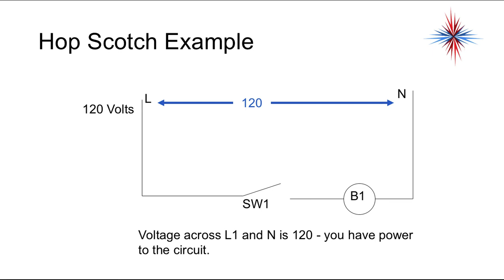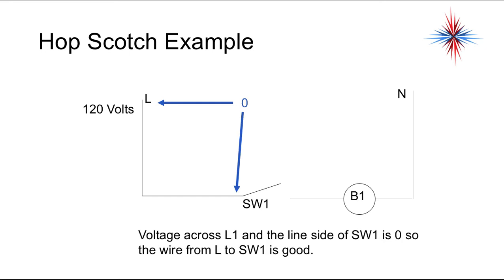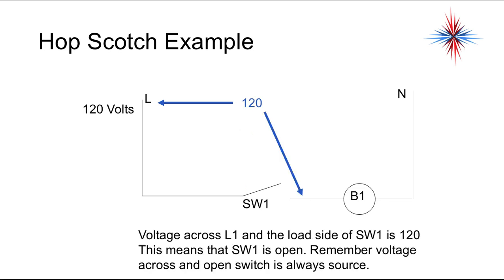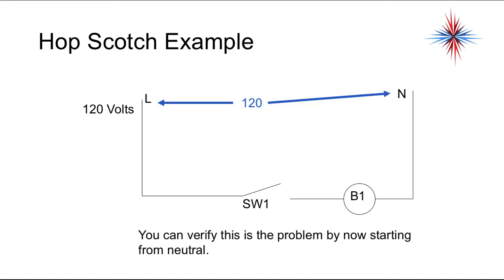So we're going to start with L1 and N. We want to make sure we have power to the circuit. Now I'm going to leave one lead clamped on to L1 and move the other to the line side of switch 1. So we have 0, so the wire from L1 to switch 1 is good. Now, voltage across L1 and the load side of S1 is 120 volts, which means switch 1 is open. Remember, the voltage across an open switch is always source.